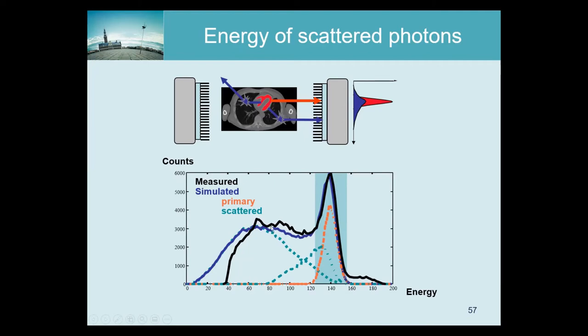We can ask the gamma camera for every photon what energy did you believe the photon had and that's the black line. And you see that the black line deviates here and the reason is that the gamma camera doesn't bother to store these low energy photons, but the simulator happily continues. So we don't care because we never use these photons here. And then you see here that in the real gamma camera, every now and then photons are detected with more than 140, really way more than 140 kiloelectron volt, and that doesn't happen in the simulation. Any reason where these photons are coming from? Any idea where these are coming from?